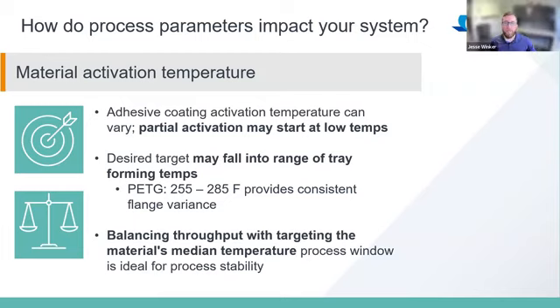Yeah, and from a tray standpoint, one of the things we're going to hit on in the next slide as well is tray materials. One of the most common materials we use from a sterile barrier system standpoint is PETG. PETG's forming temperature range is typically 255 to 285. It can fall anywhere within there depending on the design and where the specific design wants to form. You can form trays as low as 255 technically, and as high as 285, maybe even a little bit more. That's typically where we're at from a thermoforming standpoint.